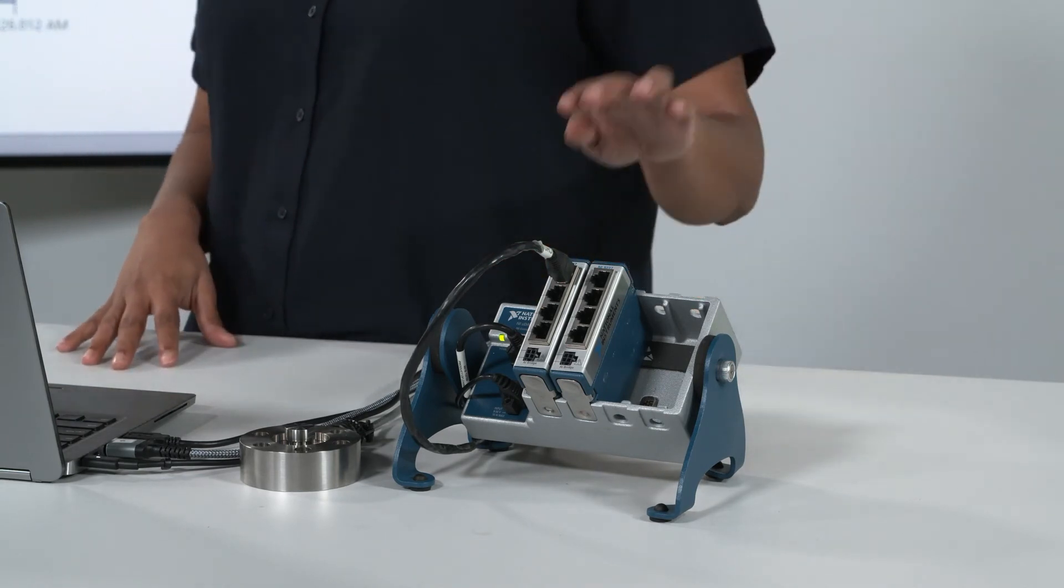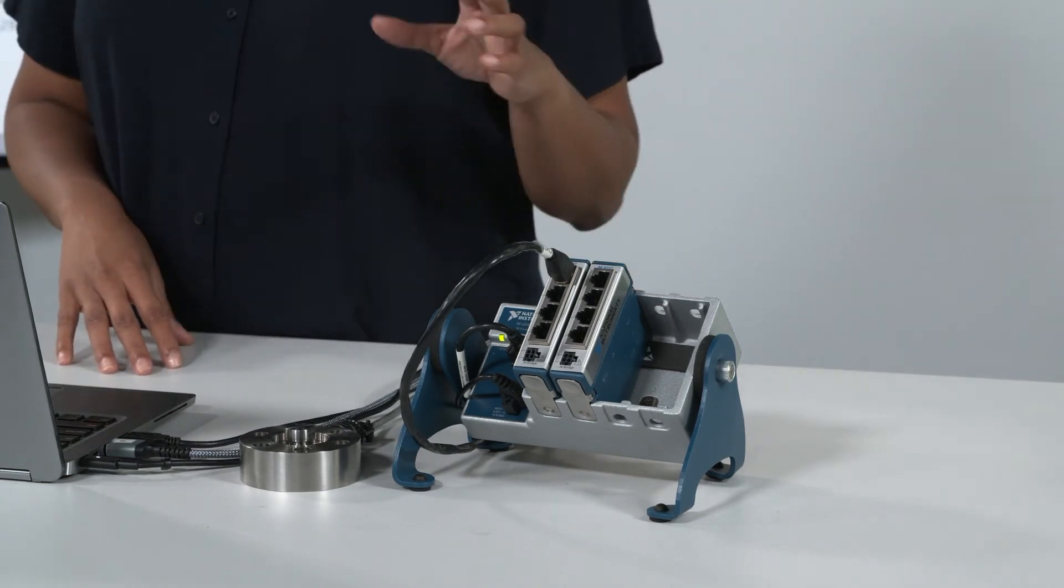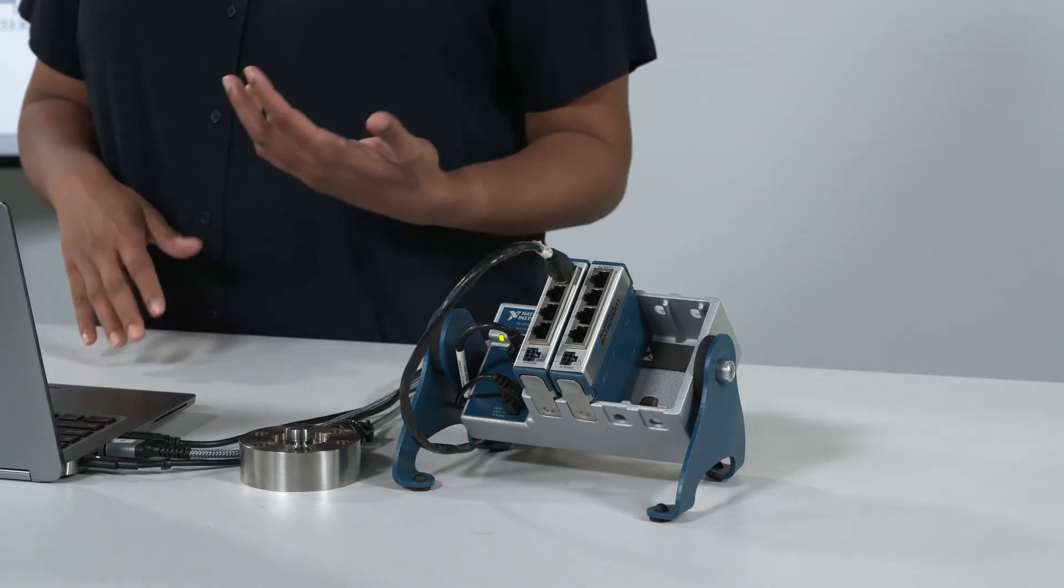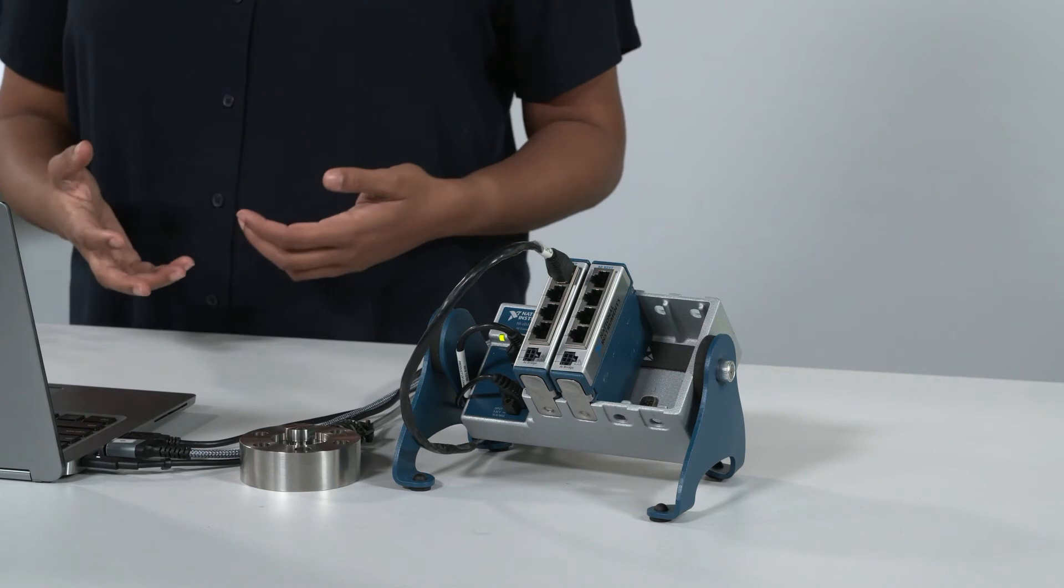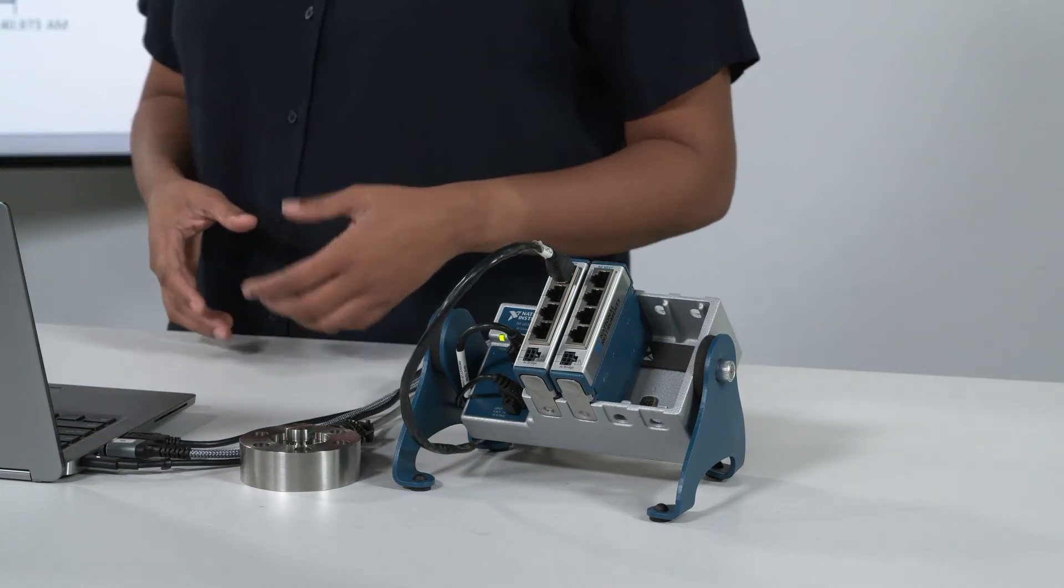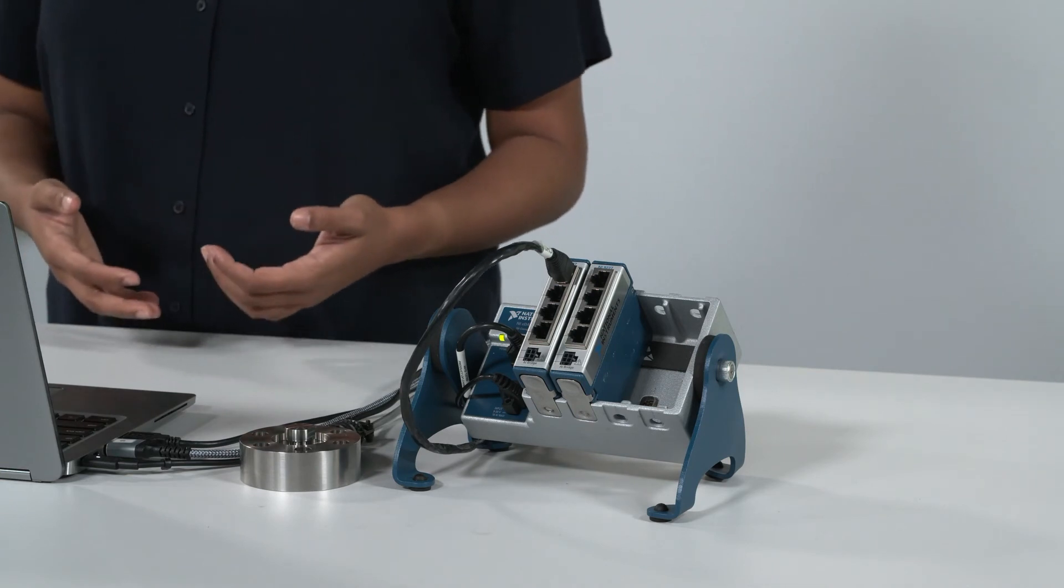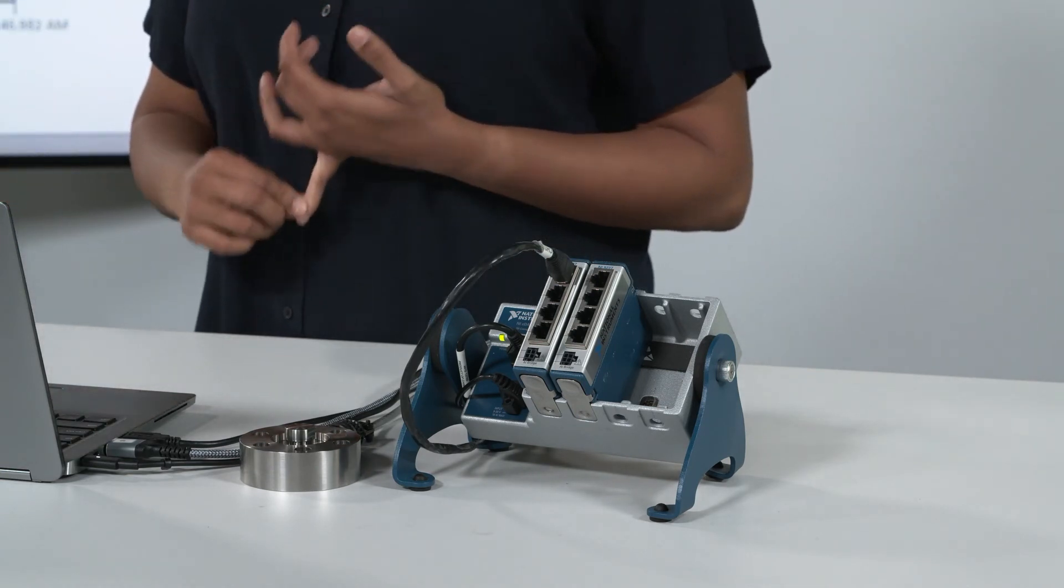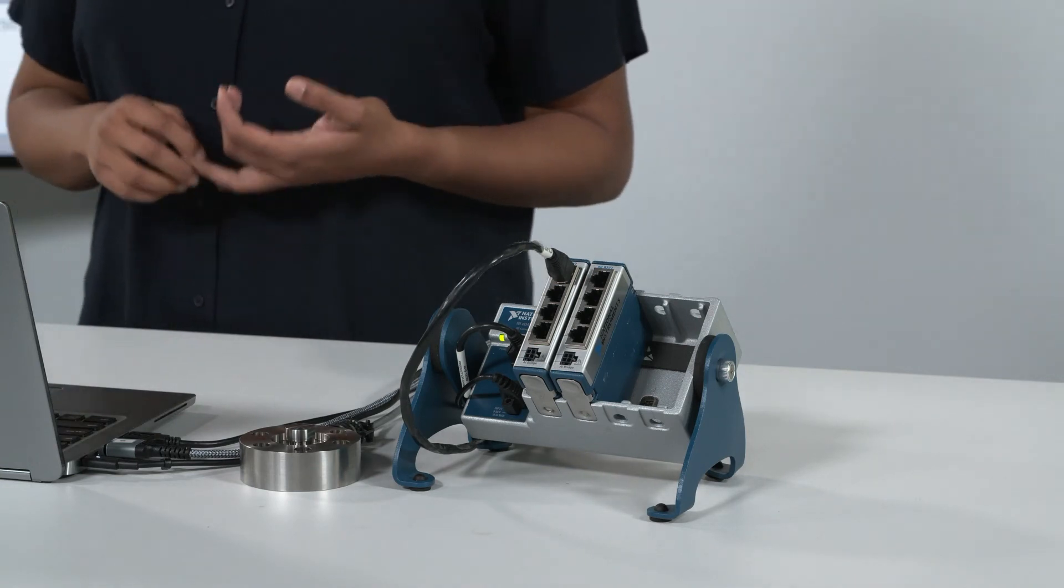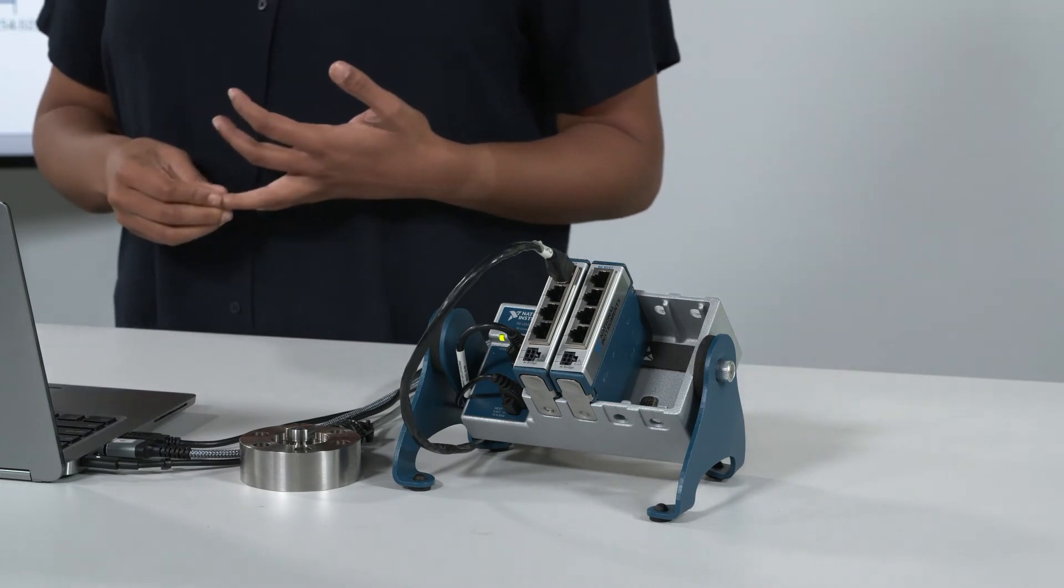The modules in the system are the 9237s. These are specifically designed for strain and load. What that means is while NI has generic analog input and output modules, this is specifically designed and specially made so it has some of those basic modifications, such as bridge completion of 120 to 350 ohms, as well as dynamic measurements up to 50 kilosamples.